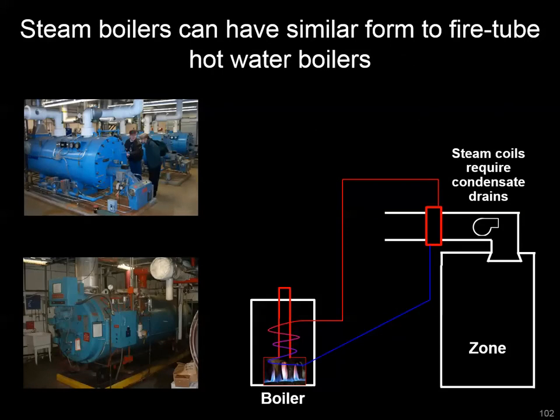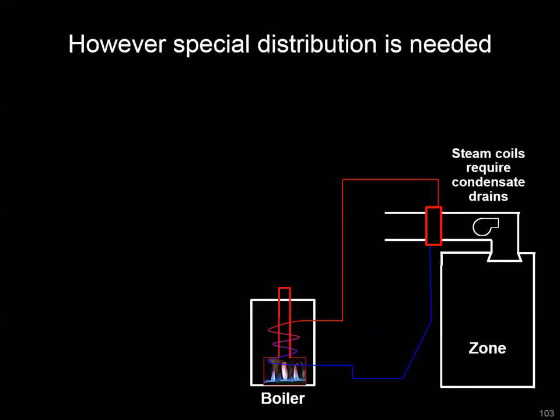The steam boiler itself can look very similar to a hot water boiler. Looking at the picture, there are a couple of clues: at the top, you can see an equal line size going in and out of the boiler — that's your hot water supply and return. On the bottom, you don't see that equal line size; instead, off to the top right, you see a steam supply manifold. Beyond that visual clue, there's special infrastructure with steam that you want to take note of, including steam traps.